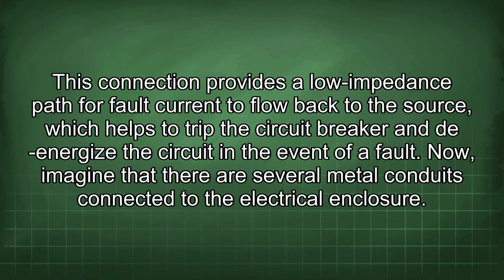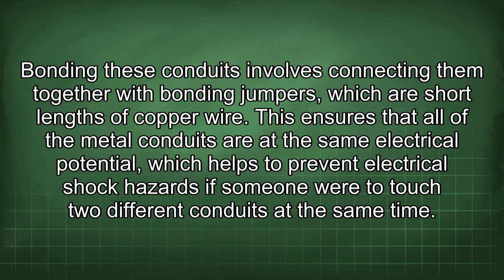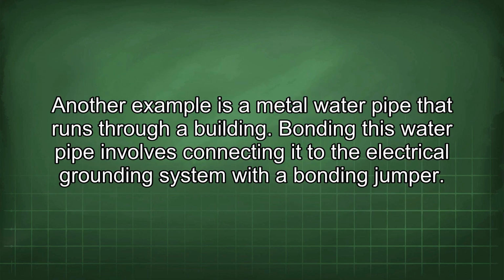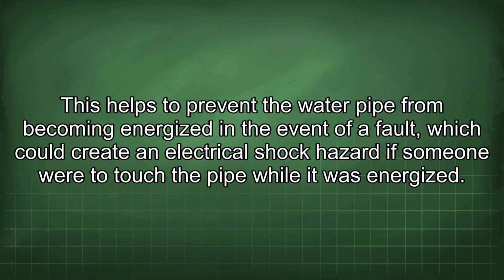Now, imagine that there are several metal conduits connected to the electrical enclosure. Bonding these conduits involves connecting them together with bonding jumpers, which are short lengths of copper wire. This ensures that all of the metal conduits are at the same electrical potential, which helps to prevent electrical shock hazards if someone were to touch two different conduits at the same time. Another example is a metal water pipe that runs through a building. Bonding this water pipe involves connecting it to the electrical grounding system with a bonding jumper. This helps to prevent the water pipe from becoming energized in the event of a fault, which could create an electrical shock hazard if someone were to touch the pipe while it was energized.